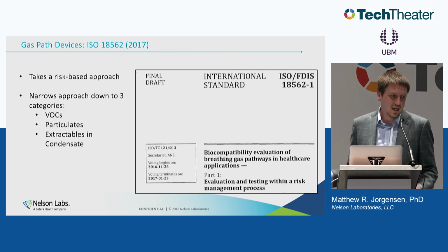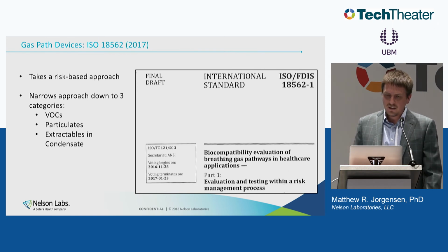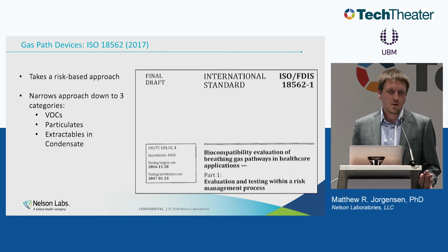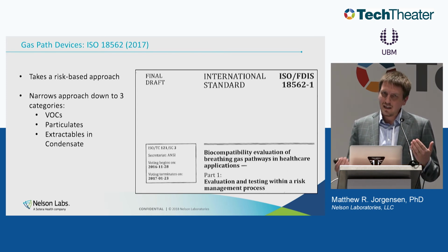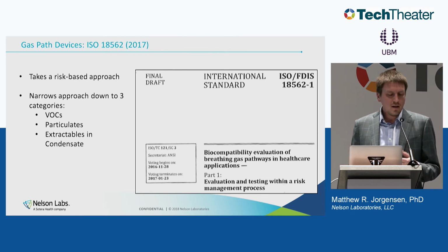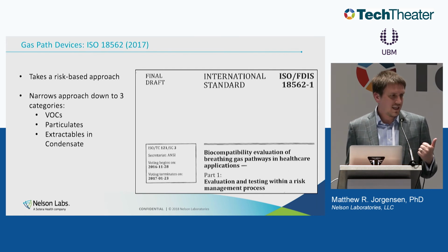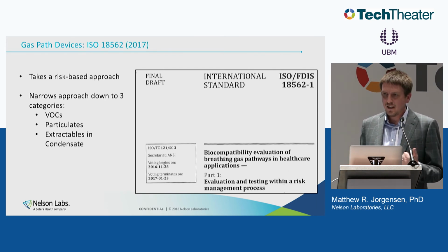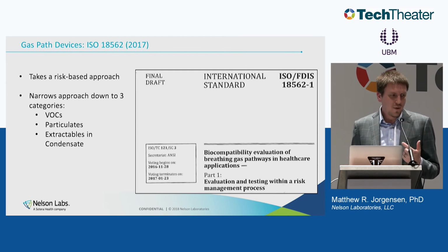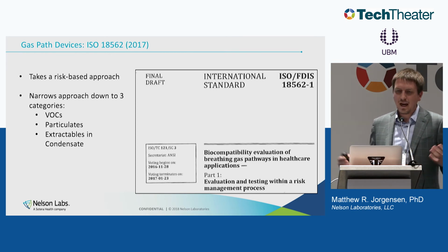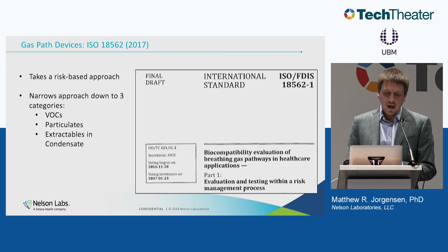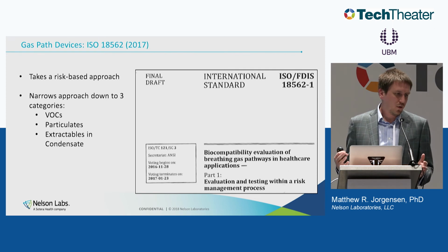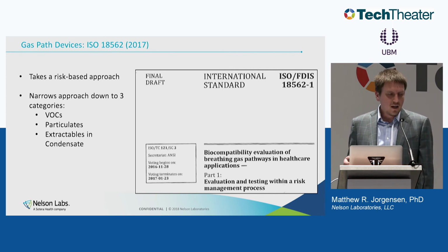So this, I think, is like a gift from heaven, especially if you have gas path devices, and it's really common sense. If you ask yourself, what's the risk associated with a gas path device? It's basically just what can contact you through the gas. And so that's what we test. We test for volatile organics in the gas from a device or passing through the device, and we also look for particulates. Those are the two main tests for a gas path device. And if you have something like an oxygen concentrator or an oxygen tank, where the only contact with the patient is through the gas, then these are really the only two tests that you need to do: volatile organics in the gas and particulates. The whole situation becomes a lot more simple and a lot more straightforward to address the risk.